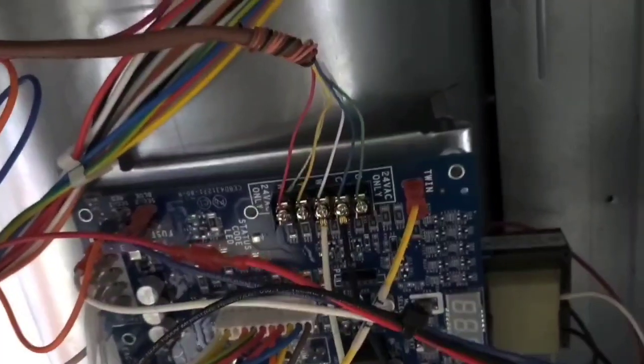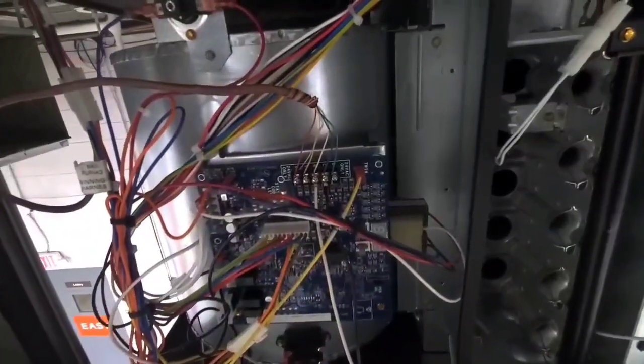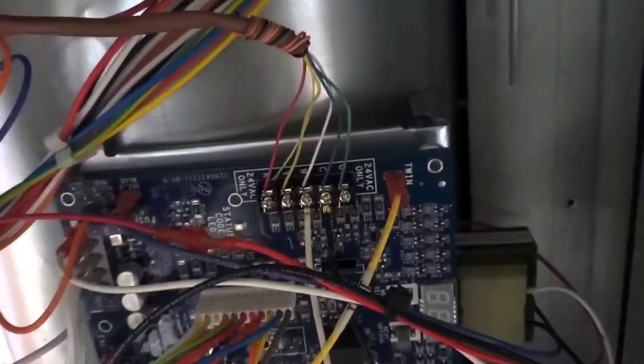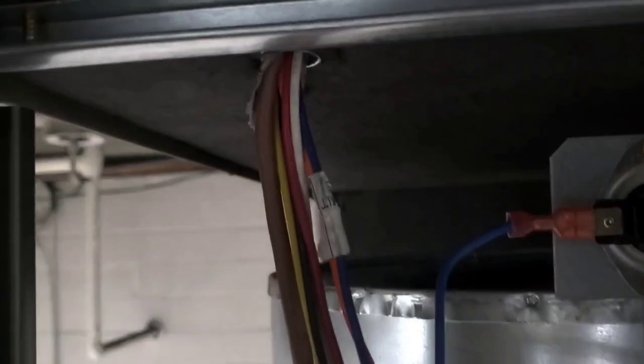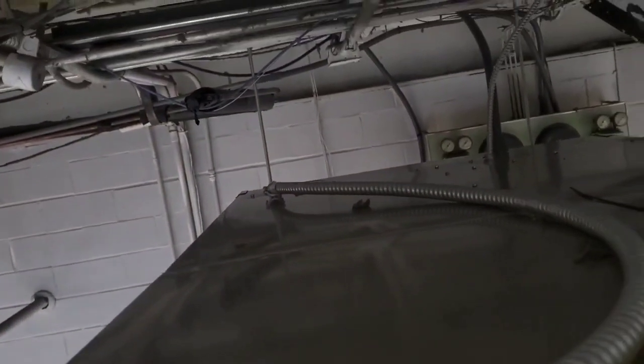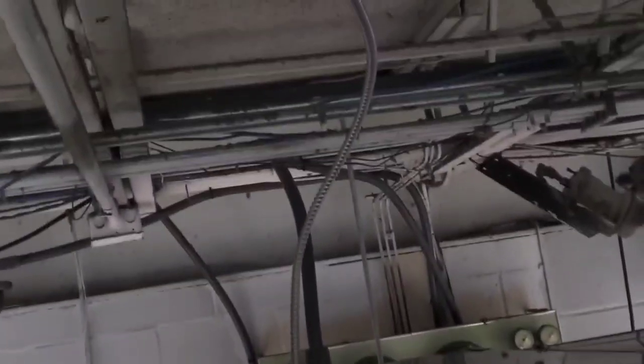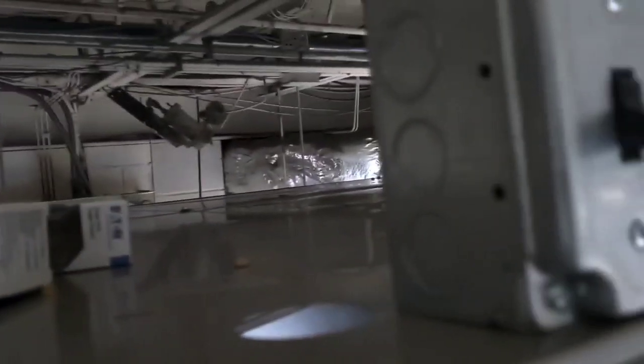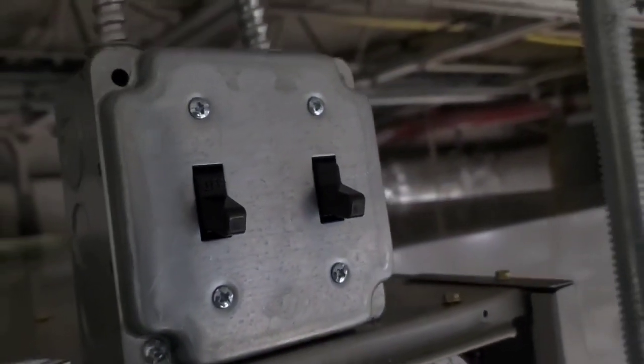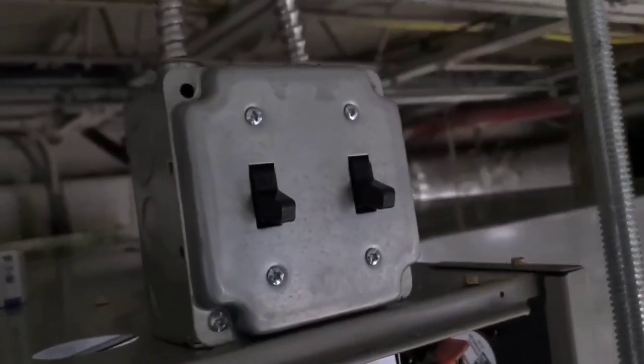Here's our low voltage connections here on our master unit. And they go up here through the twinning harness over to the slave unit because that's where the thermostat's going in, right there. Because that convenient conduit that was already there happens to line up perfectly. I put both of the disconnects right here on the master unit. So to turn that one over there off, you got to come over here.